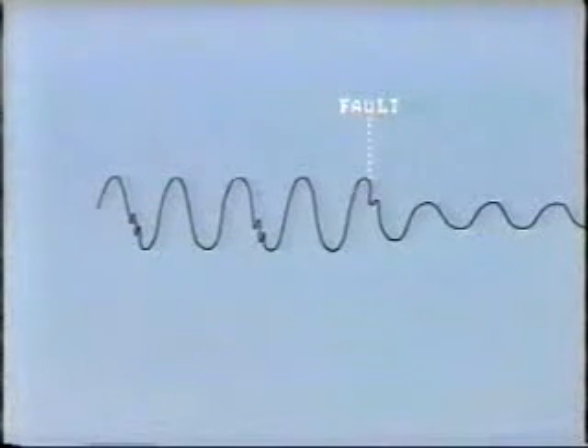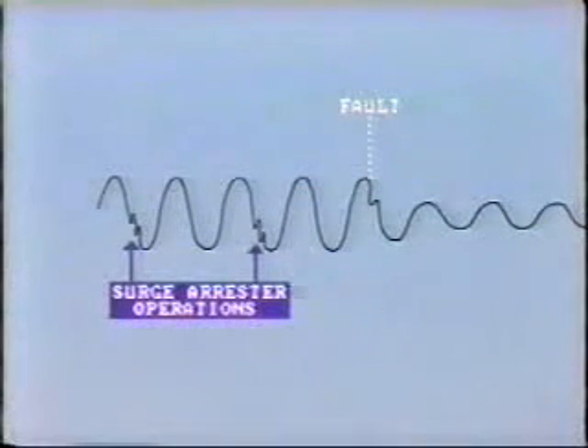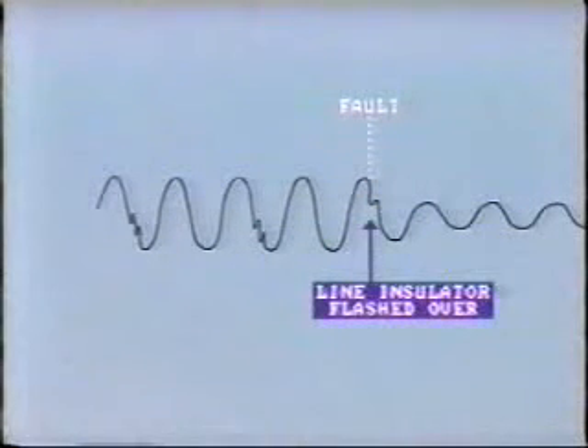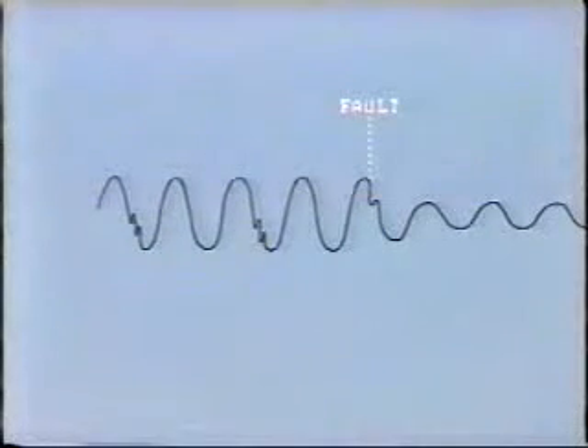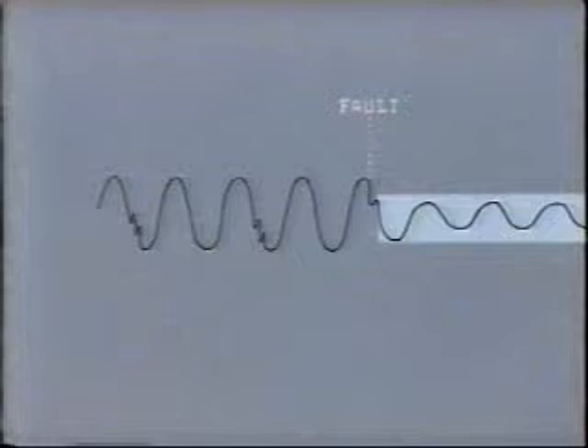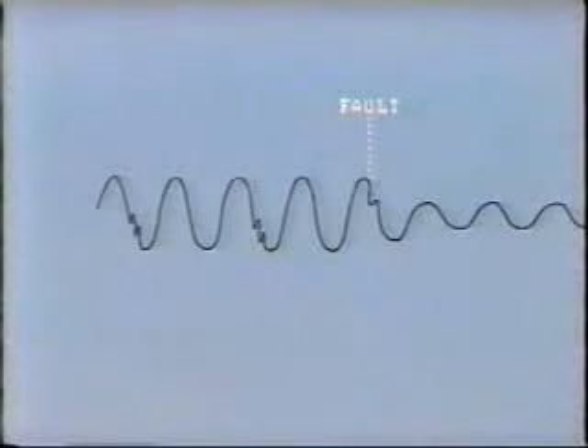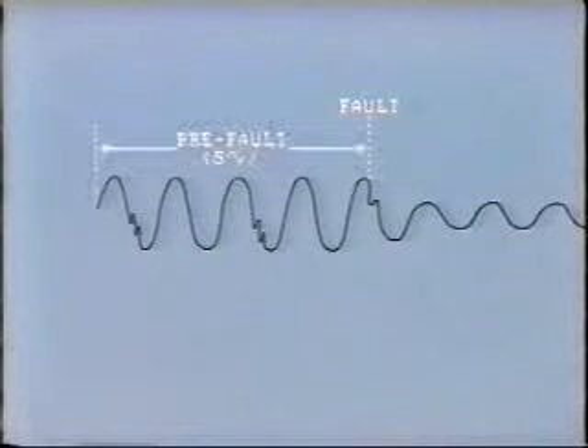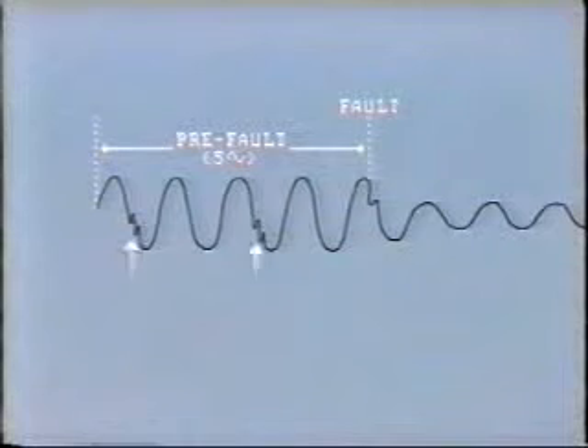This trace shows B phase to neutral voltage on a transmission line during a lightning storm. Look carefully at these points. Here we see the high-frequency effects of arresters operating and conducting surge current to ground. Subsequently, at this point, the high voltage associated with the lightning surge flashed over the line insulators, creating a temporary phase-to-ground fault. You can see the dramatic decrease in voltage due to the fault. This particular recording was started automatically when the fault occurred and captured about 5 cycles of pre-fault data. Because of the pre-fault capability, we can see the effect of the lightning arresters.